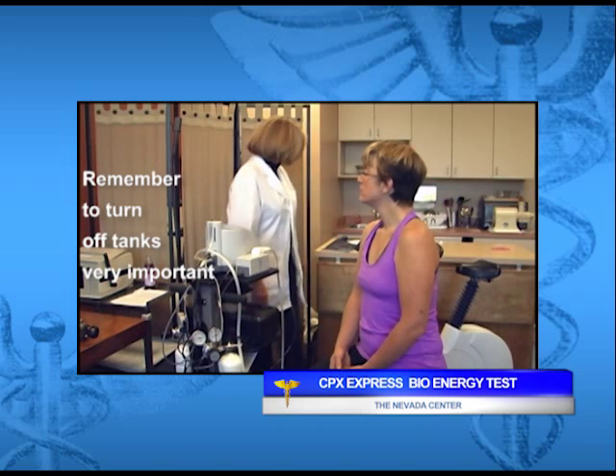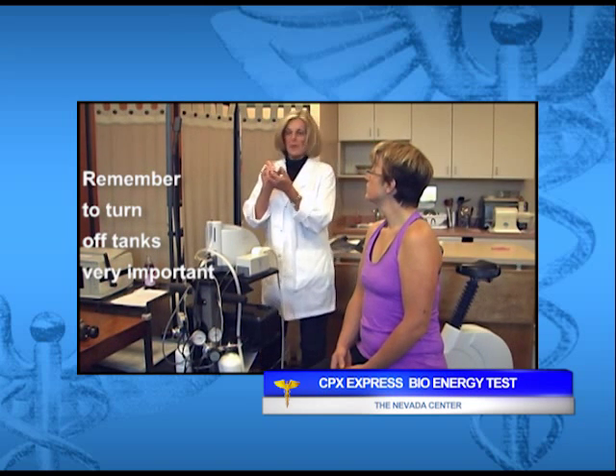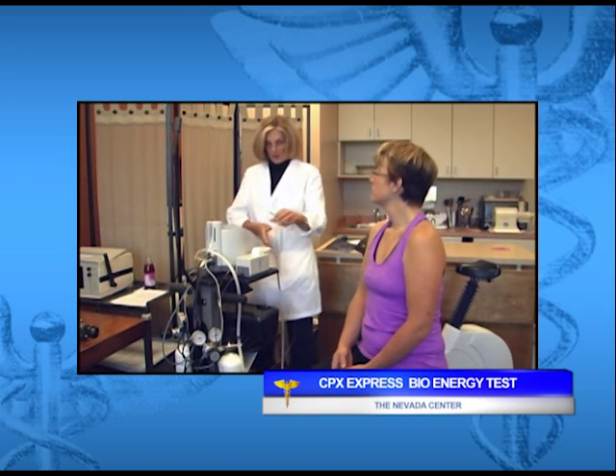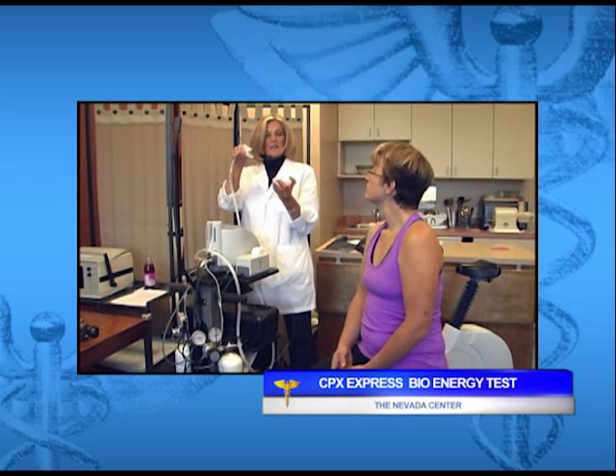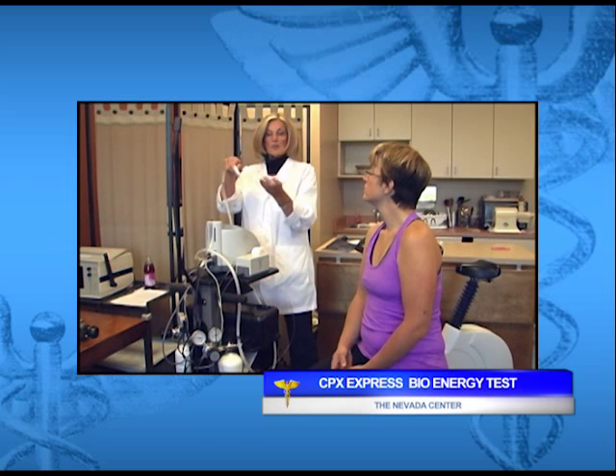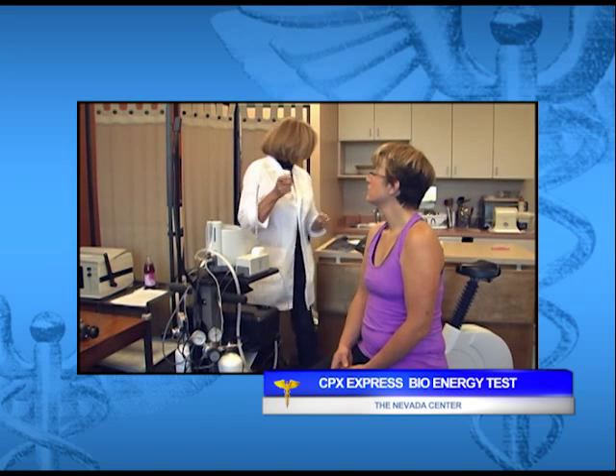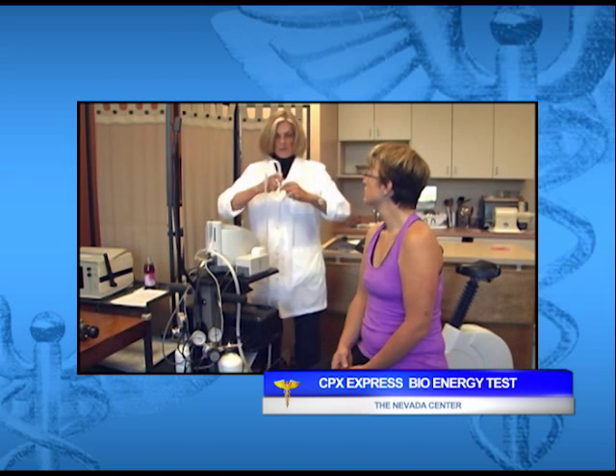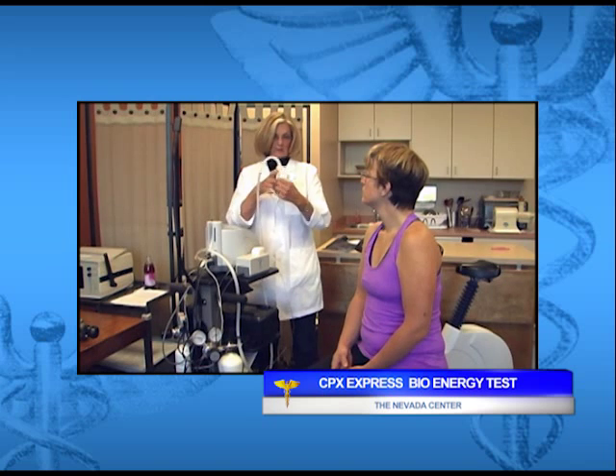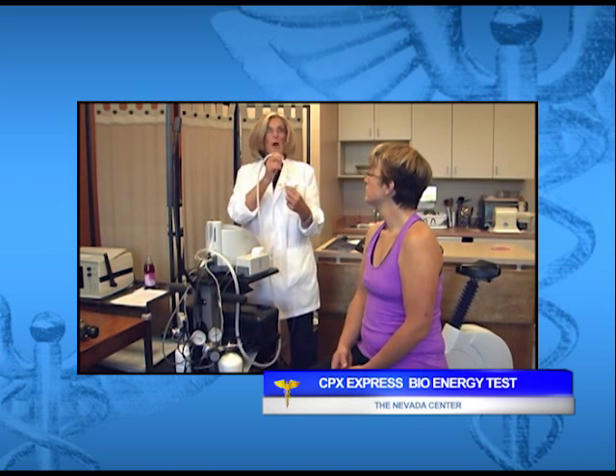Now we're going to get the pneumotach prepared. This is the pneumotach. It has a perforated side, and an open side. You're going to take your umbilical. You're going to make sure this is seated properly with the notch to the indentation on the pneumotach. You're going to insert that. After that, you're going to put it into your mouthpiece. Make sure the umbilical is always up.